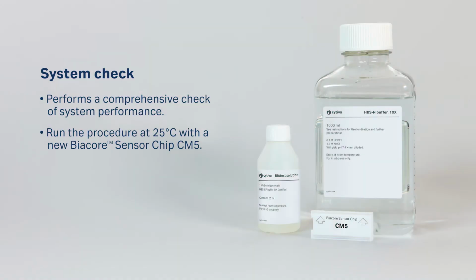System check. This procedure performs a check of system performance using a standard Biatest solution. Total runtime is 90 minutes, and the recommendation is to check once a month. A new sensor CM5 chip is required and freshly prepared HBSN and Biatest solution.